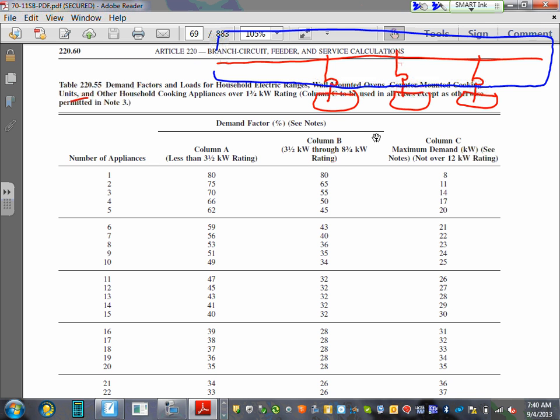Let's just put the circuit breaker right here and bring it right here, okay? And we need to size the feeder. So everybody knows that this is a feeder, and these are the bottom ones here. Okay, so these are the branch circuits that we have. So I have an apartment building. Guys, taking a feeder into a panel and feeding 3 different ranges or cooking units, or whatever you want to call them. And I'm going to give you sizes for them.